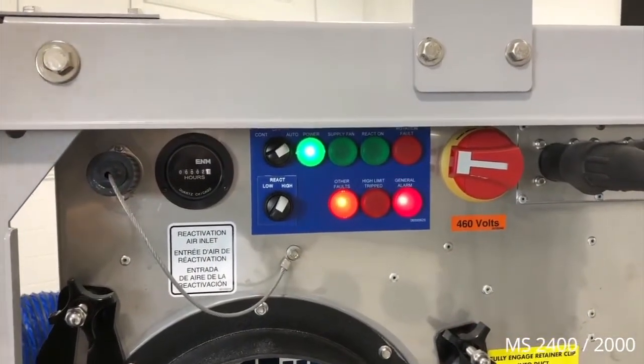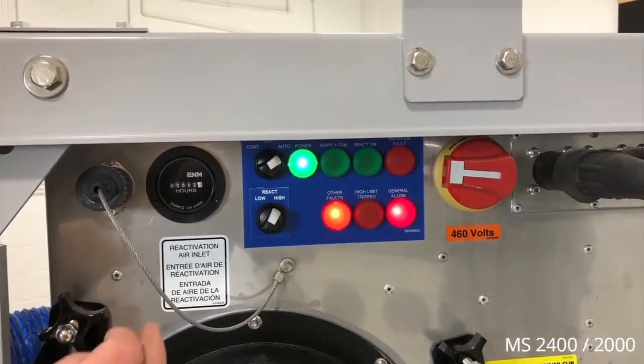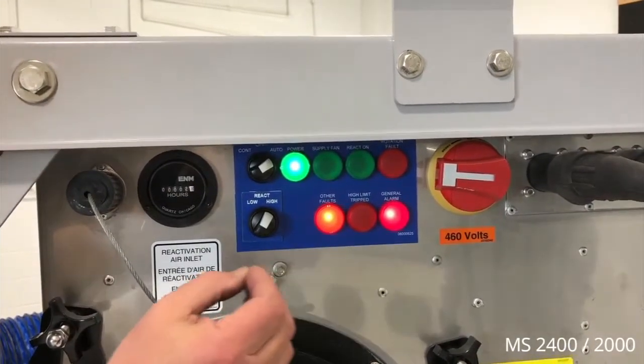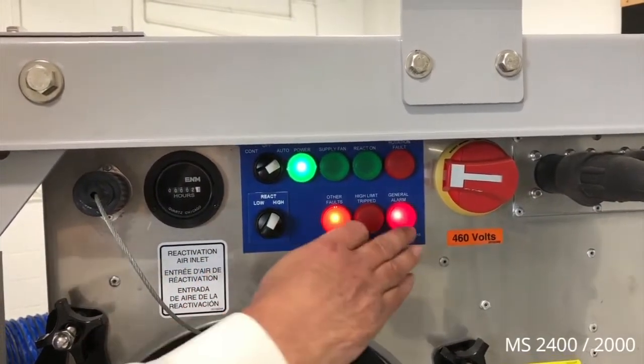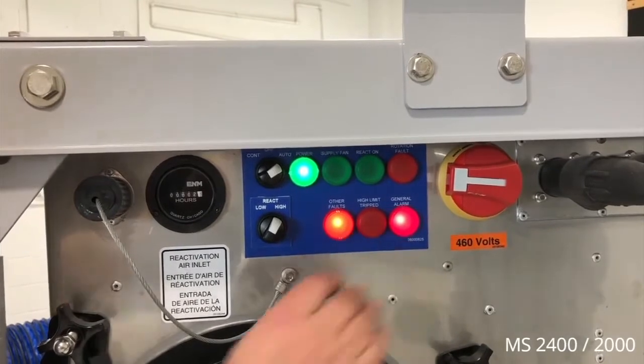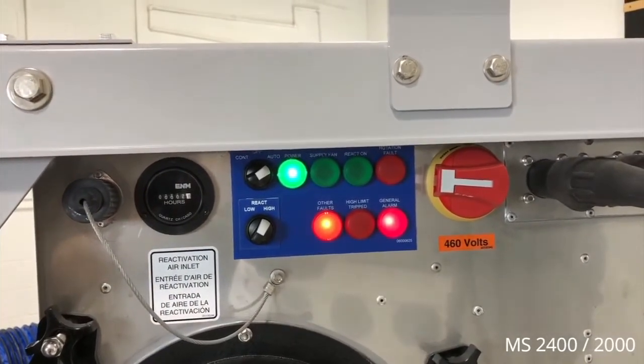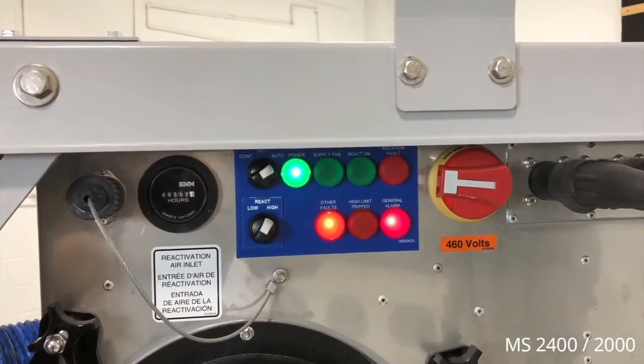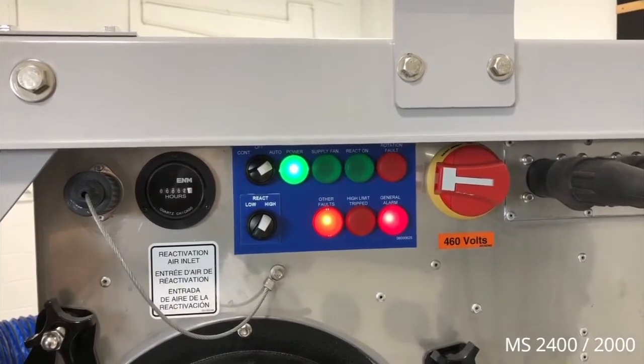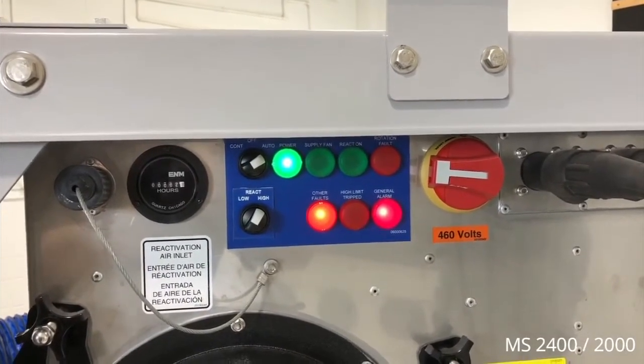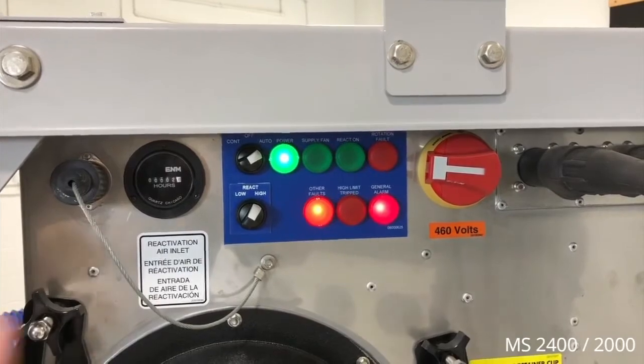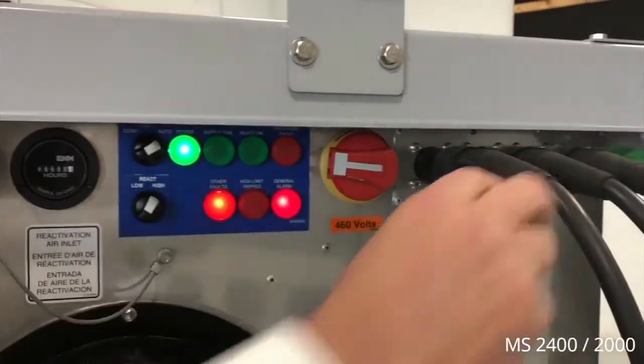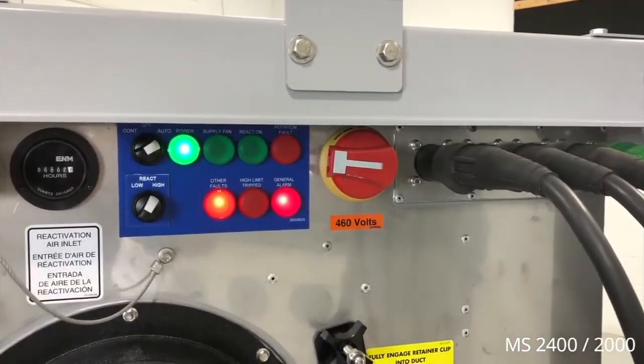After the microprocessor did its self-check, it started checking through the circuits and found that we have other faults and a general alarm. Both of these, upon startup, normally will indicate an out-of-phase situation. So in that event, we have to cut the power to the unit and cut the power to the generator and reverse 2 of the power leads to bring the unit back into phase.